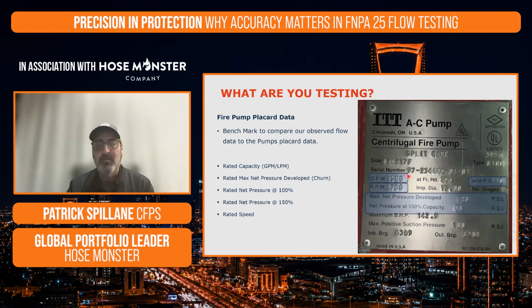So while flowing 1,500 gallons a minute, we should see a differential net pressure of 110 PSI on this fire pump. However, when we're flowing 150% of the fire pump's rating, so when this fire pump is flowing 2,250 gallons a minute, we should see a net pressure that's going to drop off, right? We need to see a net pressure of 88 PSI. And then as well as our churn pressure when we first turn that fire pump on, that's going to be our max net pressure developed here. So on this placard, that means that we don't want to see a net pressure higher than 125 while that fire pump is churning.